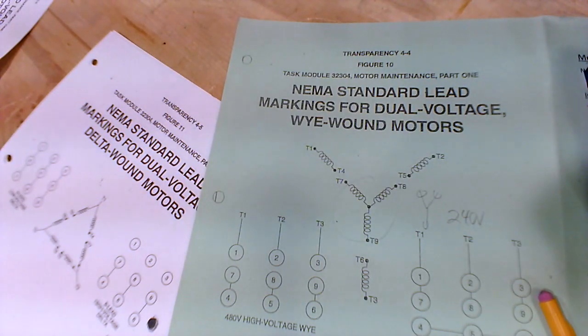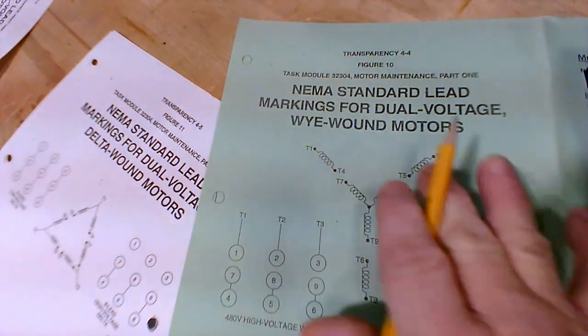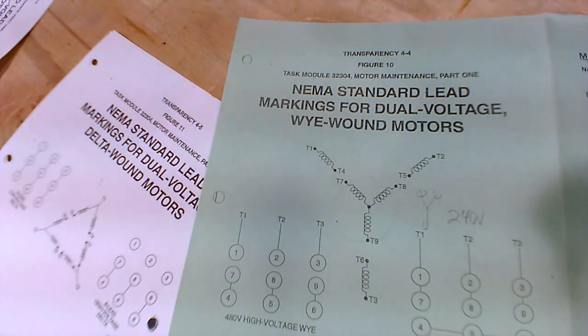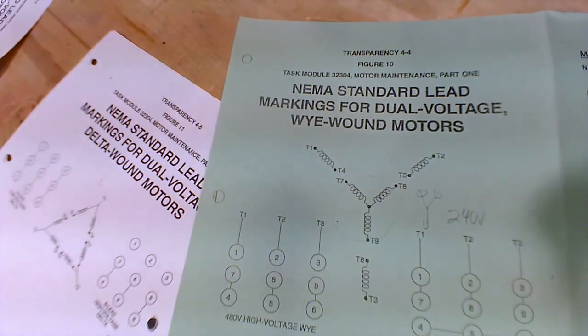Okay? And that's the way most motors I've worked on are Y wound. It doesn't tell you wye on the nameplate. It doesn't tell you that because most motors are Y wound. The only time it tells you what kind of a winding it is is when you come up with something that's called a delta. So let's flip over to delta.